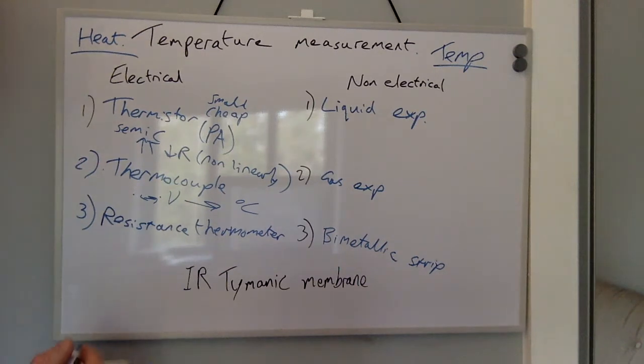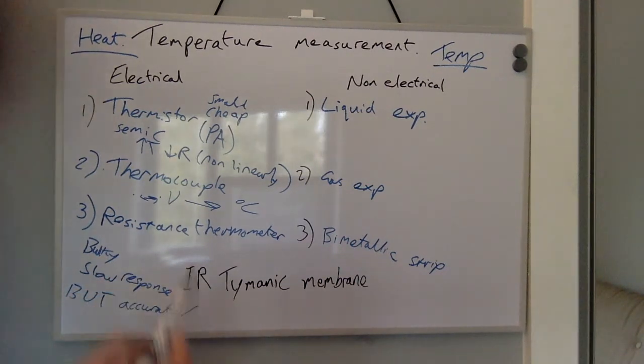Resistance thermometers are bulky and have a slow response time, but extremely accurate. The resistance thermometer works on the principle of a platinum wire.